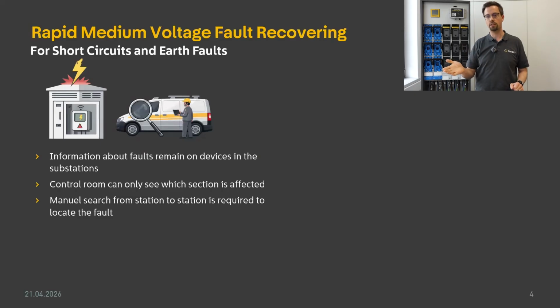So you go out to the first station, you look at the fault passage indicator, and it will say upstream, downstream, left or right of this substation is where the fault is. Close that one up, drive to the next station, look in there - that will also tell you the direction. You keep going until you find the station that points back in the direction you came from. Then you know it's between those two points in the network.